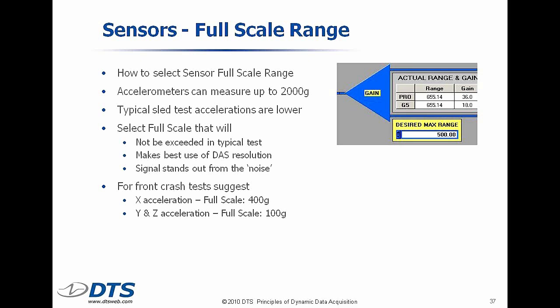So how do you select the full-scale range? Well, all the DAS products out there will say, tell us what your maximum measurement is. Basically, tell us what your channel amplitude class is. And so you put a number in, and there's sometimes a little bit of judgment in how you set that up. But for example, in the automotive crash test world, we typically tell our customers that the best performance they're going to get out of the system is going to be if they set up so that the x-axis accelerations in a frontal impact, that's the greatest, are in the range of 400 Gs.